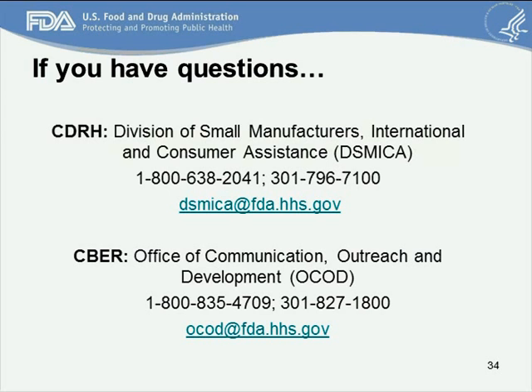If you'd like a meeting to discuss the deficiency and your approach to responding to it, yes. It might be that we asked you for A, B, and C, and you think X, Y, and Z might support it, and then you want to get our feedback before you actually respond to the 510K. That would be appropriate to have a submission issue Q-sub where we talk about whether alternate types of responses would address the underlying question that FDA had during its review.